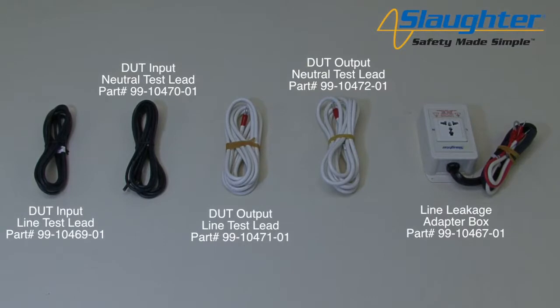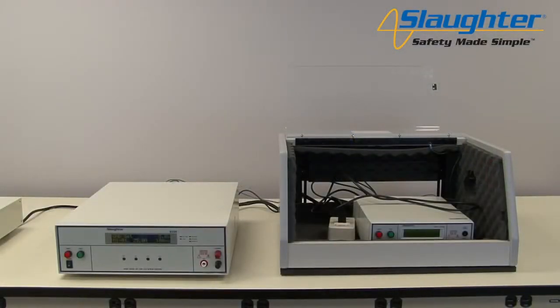You will only need to use the white output leads for the run and line leakage tests if your DUT draws more than 20 amps of current. Otherwise, you can use the line leakage adapter box to simplify your connection to the DUT. For this video demonstration, we will be using the adapter box and case lead to make the connections to our DUT. First, we need to connect an external power supply for our line leakage tests. This also applies to the run tests.